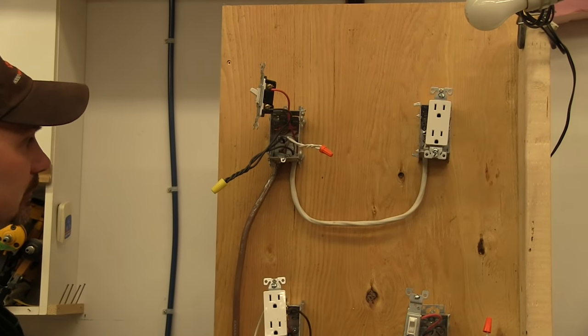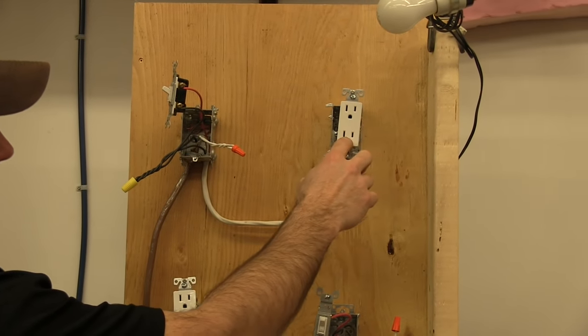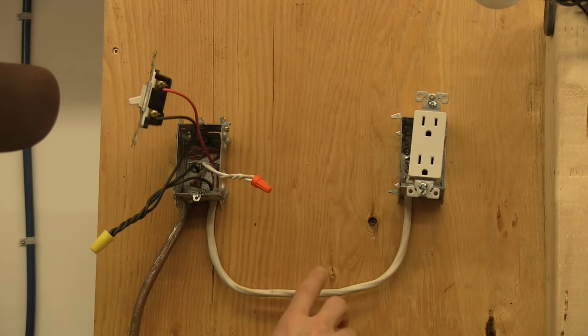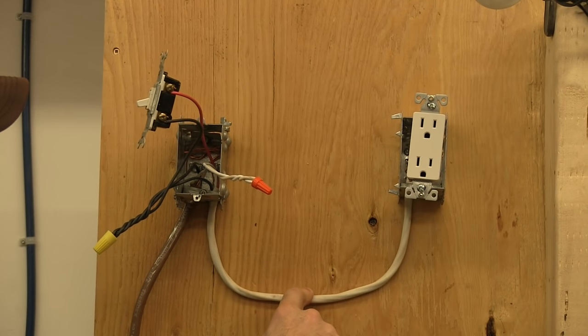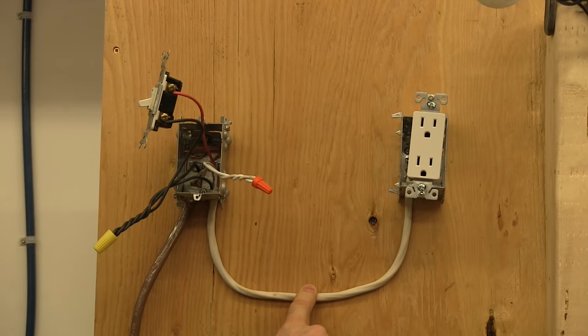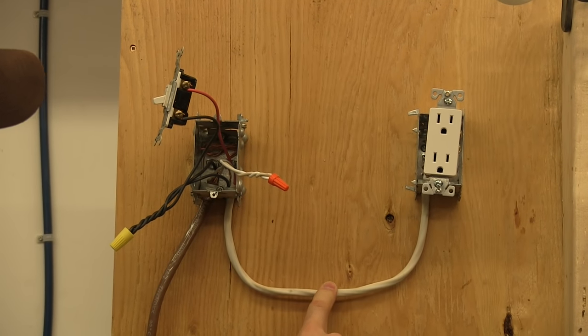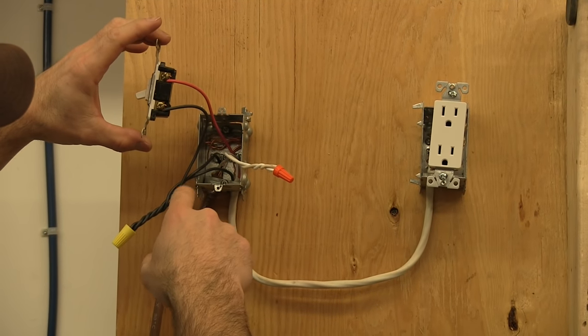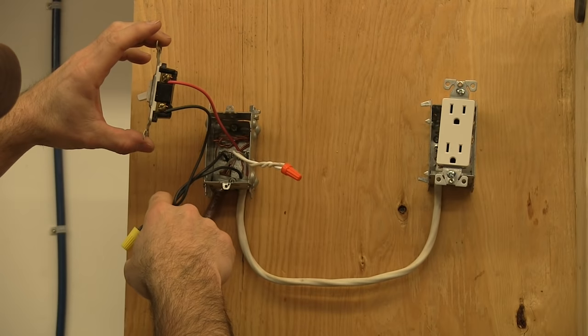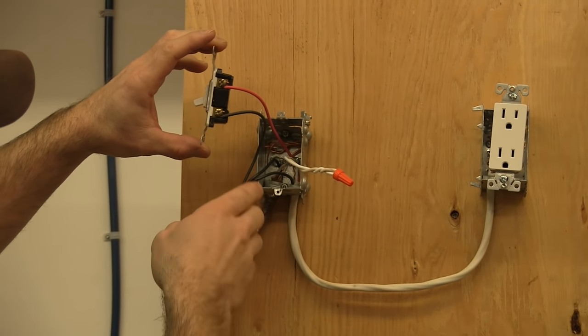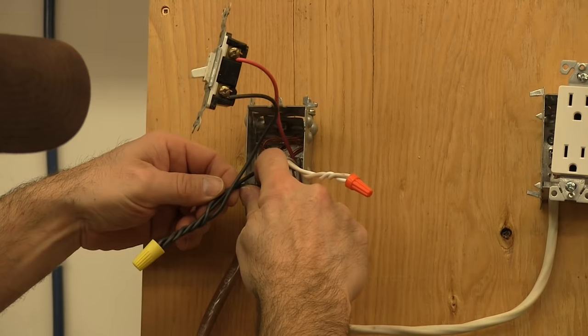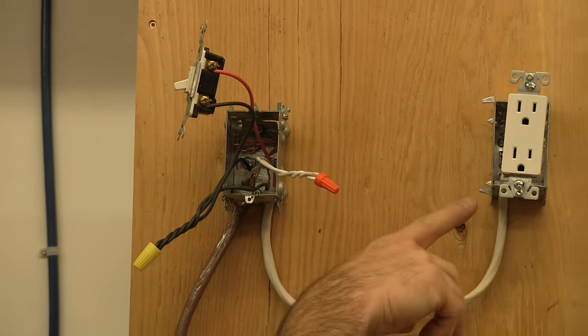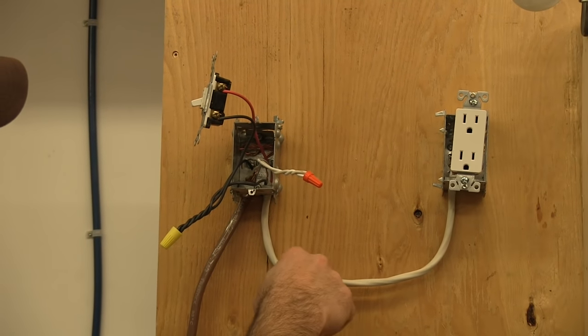In this example up here, if we wanted to have both of these powered only when the switch is turned on, what we would have to do is we wouldn't need 14-3 wire in here—we'd only need 14-2 wire or 12-2, depending on your situation. So everything right here would be all the same other than one of these wires wouldn't be in there. One of these black wires that was coming from over there or going over there wouldn't be needed. So you'd have a 14-2 here only.